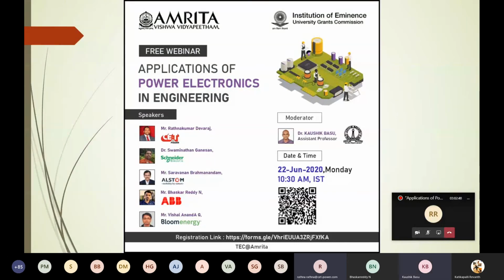So you take the DC from here, so our DC can be connected to the inverter there. Whenever the grid is present, you make a double conversion from there - you utilize the AC input grid and convert to AC output to the loads. And then when the AC is not present, you take it from the existing DC which is available in the telecom center.